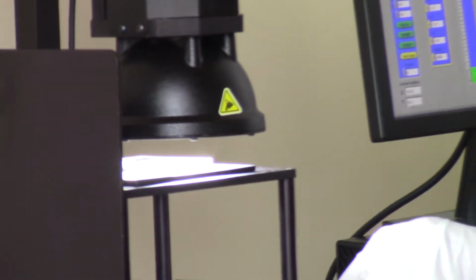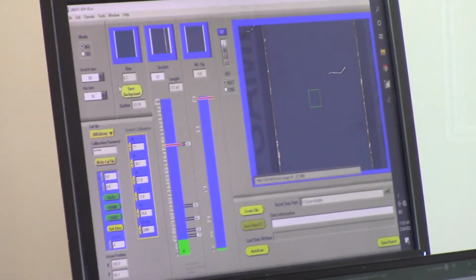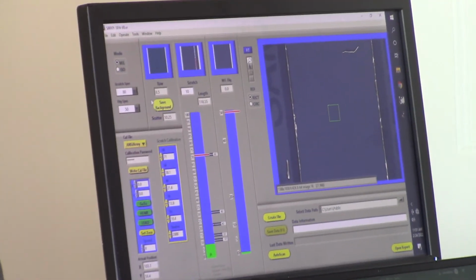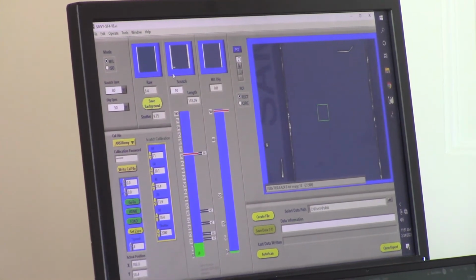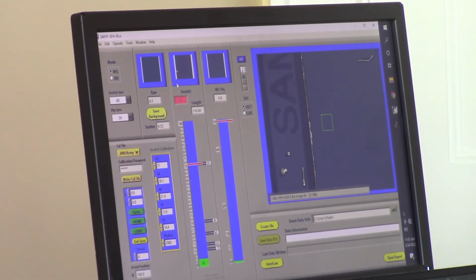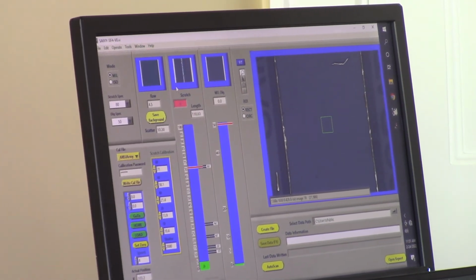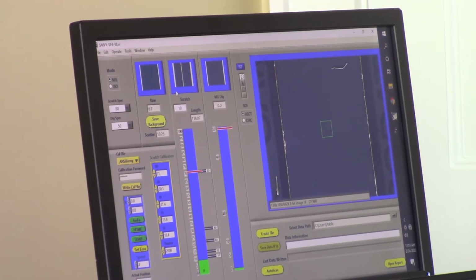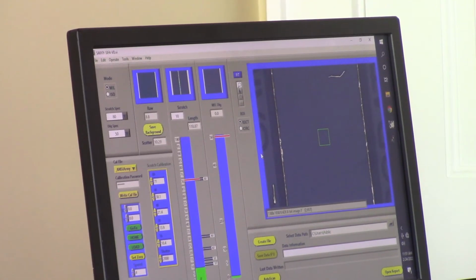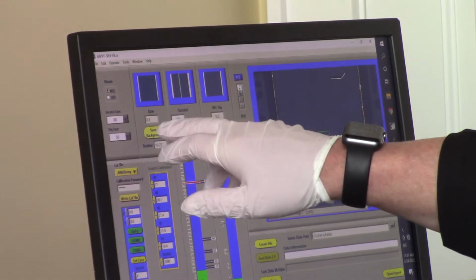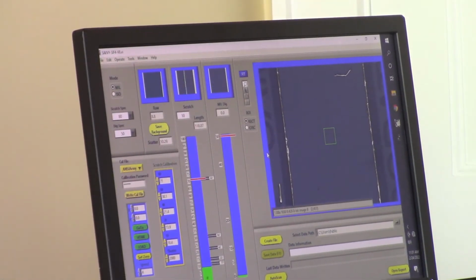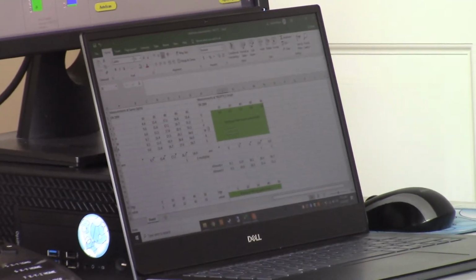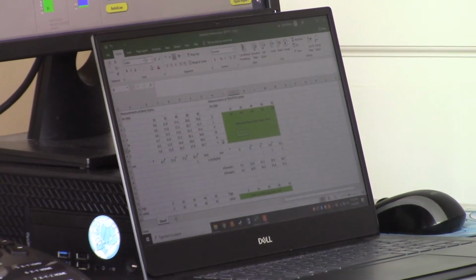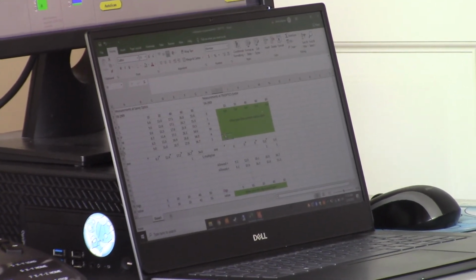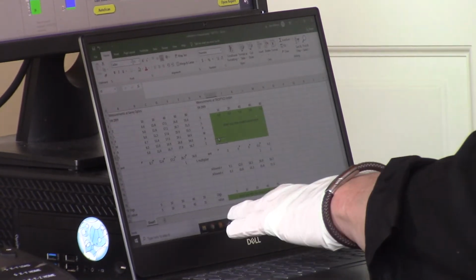So you're going to go ahead and translate the stage until you get the first of your scratches. This is the number 10 scratch. And I want to get the green box underneath the letter S on the scratch. So that's a position where I'm going to take a measurement. I take that measurement and it's at 8.8, the raw scratch value that's here. And I'm going to enter that into the spreadsheet over here. So here's the raw scratch value, and you'll see that in the spreadsheet we have a place for 6 measurements per scratch. One for S, one for A, and so on. So you'll enter the value here.